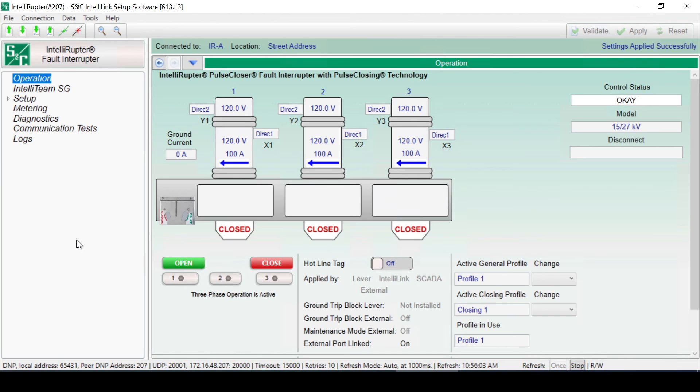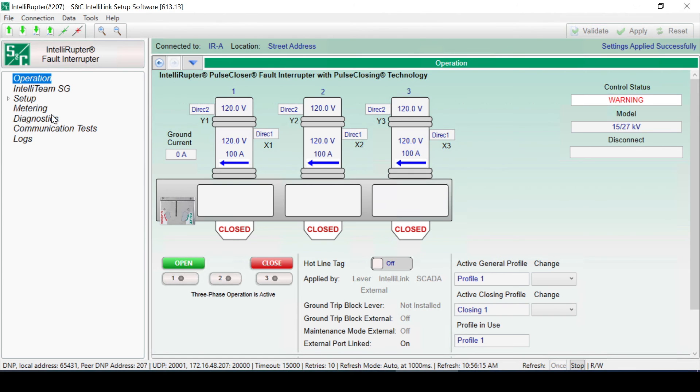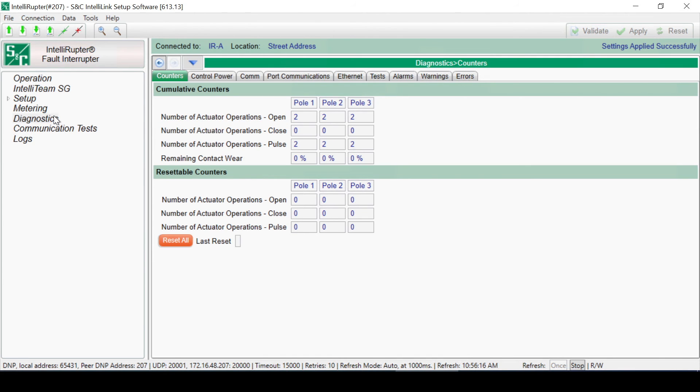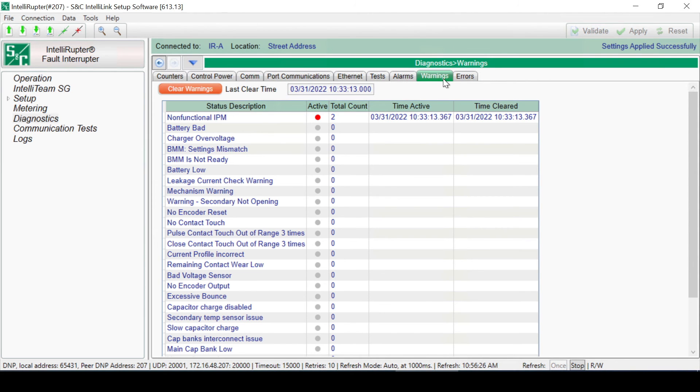Error will cause the fault interrupter to be inoperable in most situations and is common if the software is being operated without a simulator mechanism. To clear the Error, Warning, or Alarm status, navigate to the Diagnostics screen and the appropriate tab. Click on Clear Warnings, or Other Appropriate button, and the control status will change to OK.